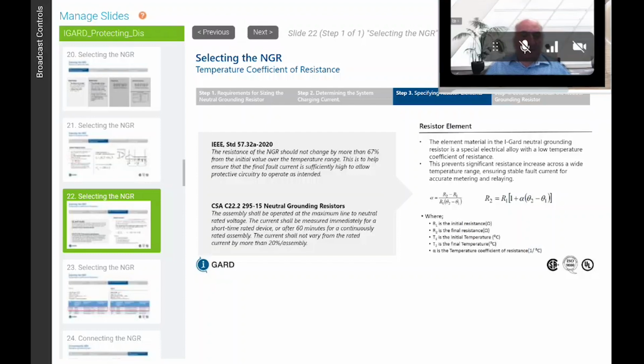So again, C57.32, 2020 suggests that the resistance of the NGR should not change by more than 67%. Now, 67% I think is a lot. In Canada, the CEC basically says your resistance should not change by more than about 25%. This is the formula to determine the change in resistance based on the material you use for the resistor. Alpha is the temperature coefficient of resistance. The final resistance of your resistor is going to be equal to your initial resistance times 1 plus alpha, the temperature coefficient of resistance, times the change in temperature.